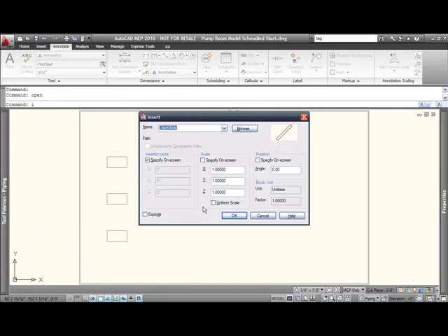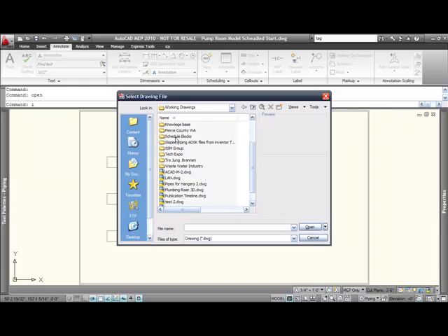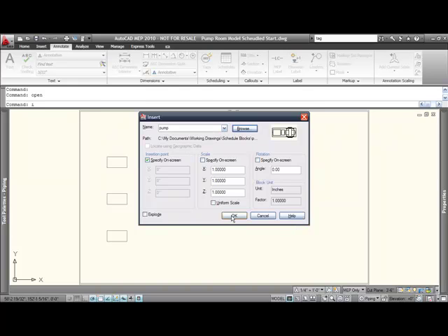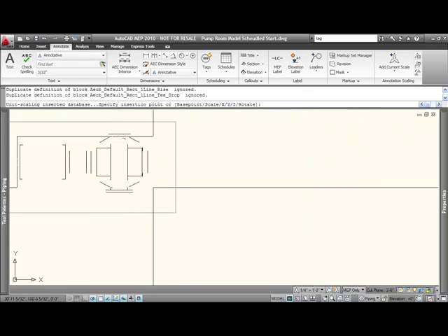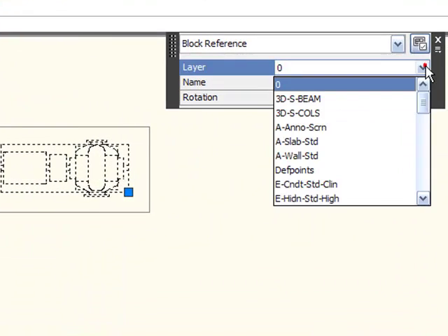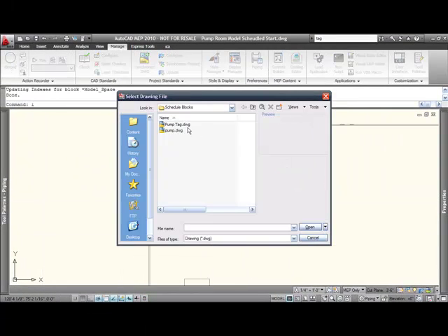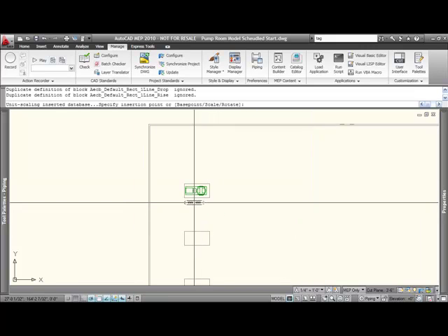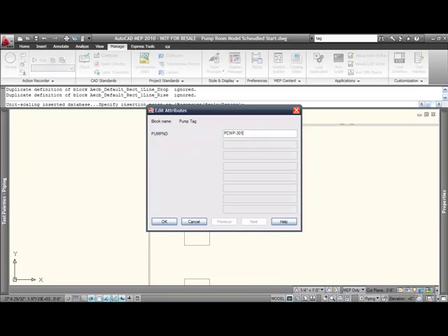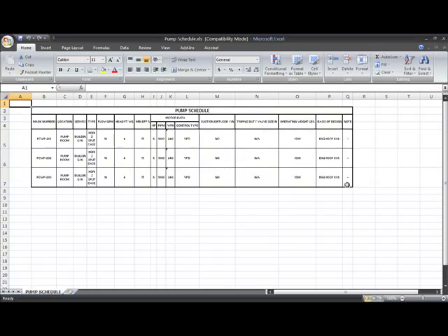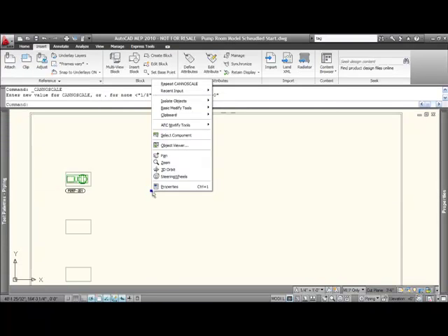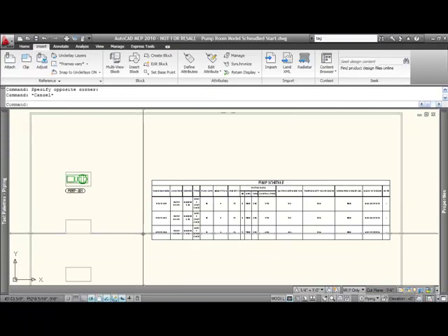So then let's compare this to the traditional AutoCAD workflow by recreating the same example. Most users will accomplish this with blocks, blocks with attributes, and copy-paste from Excel. I'll go through that now. First, we will need to insert our block for the pump. But when we do that, we will need to define the layer it belongs on. Then, we can insert the block for the tag. But again, when we do that, we have to manually manipulate the tag and place it on an appropriate layer as well. Once those are both in, we can copy-paste our schedule from Microsoft Excel into our AutoCAD environment.